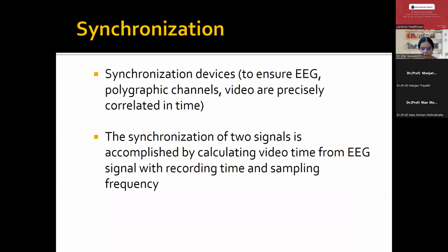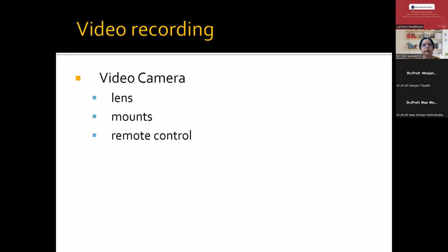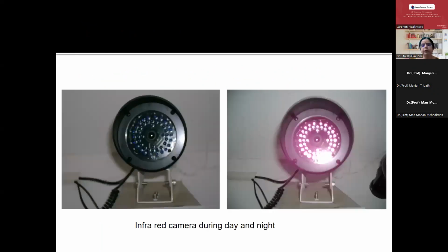Always most important in video EEG is synchronization between the EEG and the video, that is, the camera recording. The synchronization should be accomplished by calculating the video time from the EEG signal with the recording time and the sampling frequency. The video camera will have a lens. It should be mounted, and there should be a remote control available to operate the camera. The camera can have an infrared mode which can be used at night, or otherwise can record in the daytime.